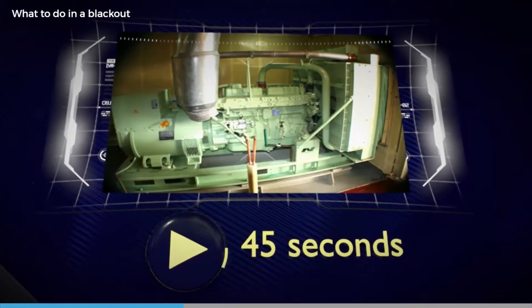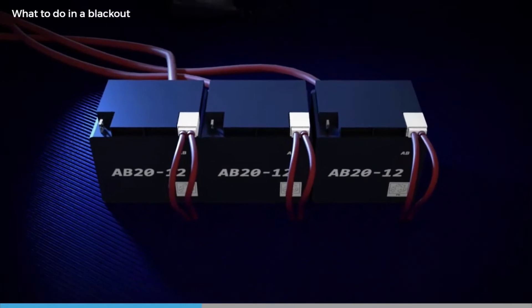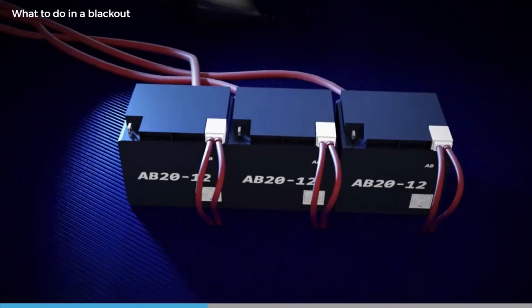Remember that the emergency generator should start and give you essential services back within 45 seconds. In the meantime, batteries should keep your alarm and monitoring systems working.